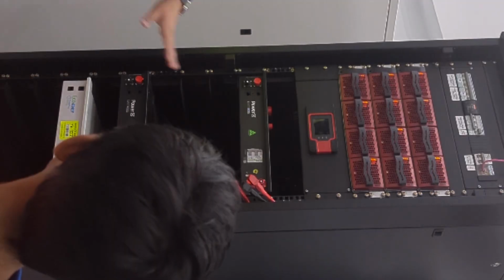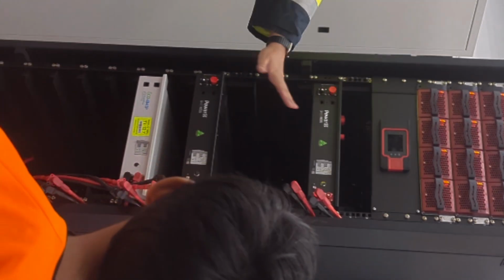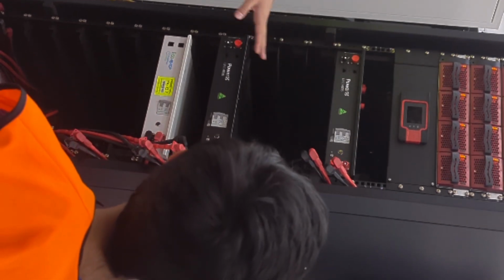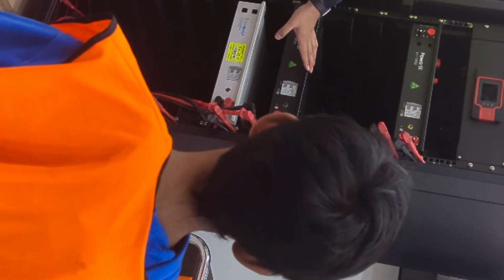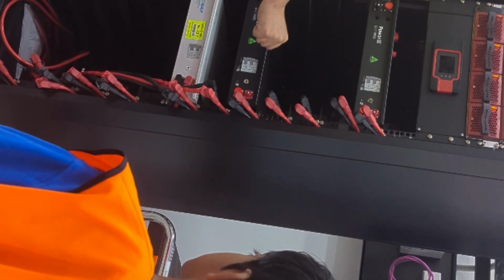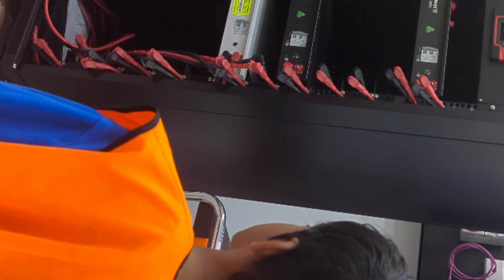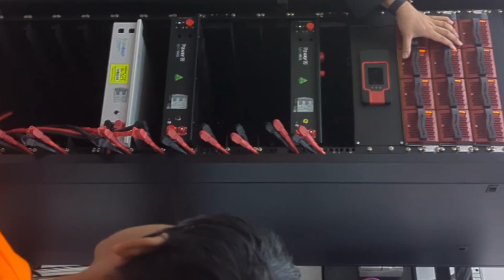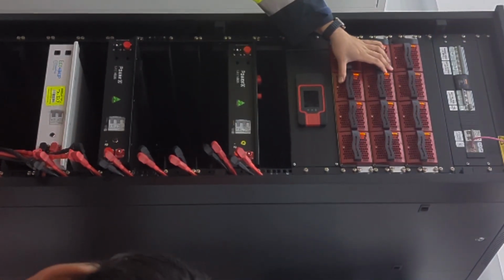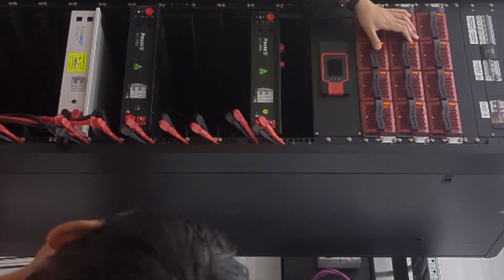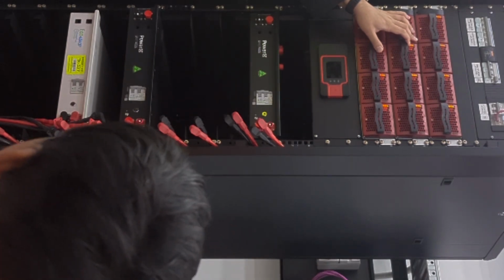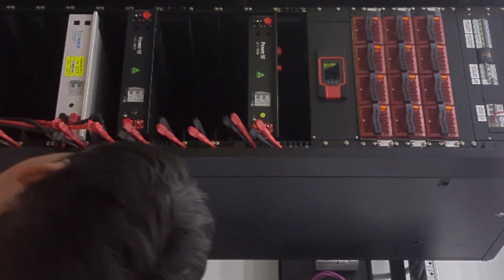It's the same with the batteries, which you can't really see here, but just say we've got 14 batteries connected. Just say you get a red light on one of them, you can turn the breaker off on that battery, pull it out while the system is alive. So a faulty battery is not going to knock over a system. A faulty inverter is not going to knock over the system. So this should result in a very small amount of calls midnight on Friday or midnight on Saturday when microgrids tend to fail. We can scale these systems up quite large.